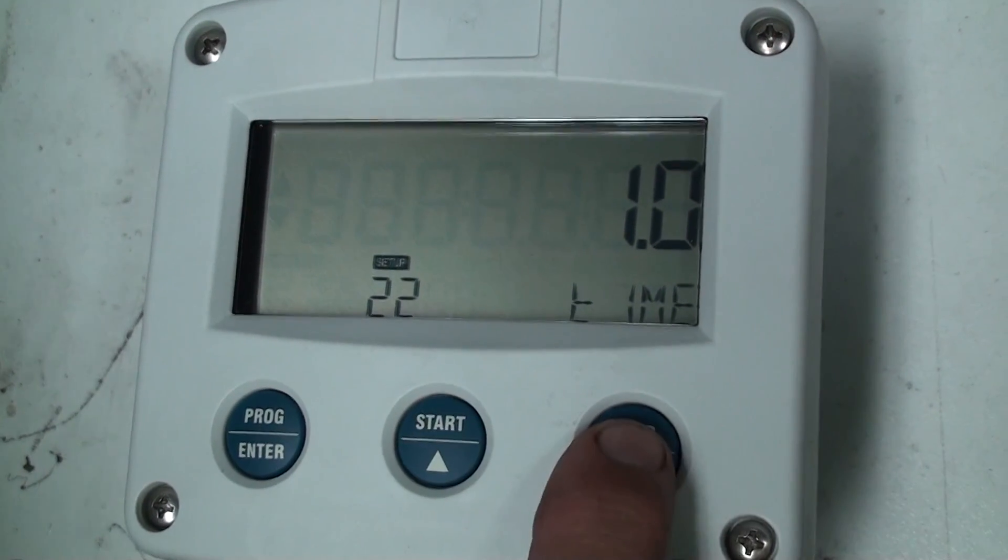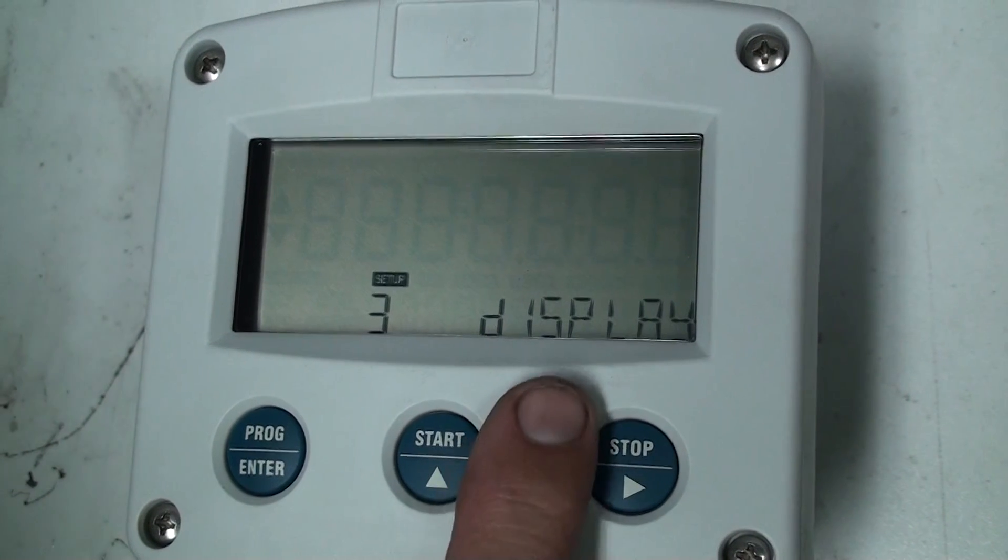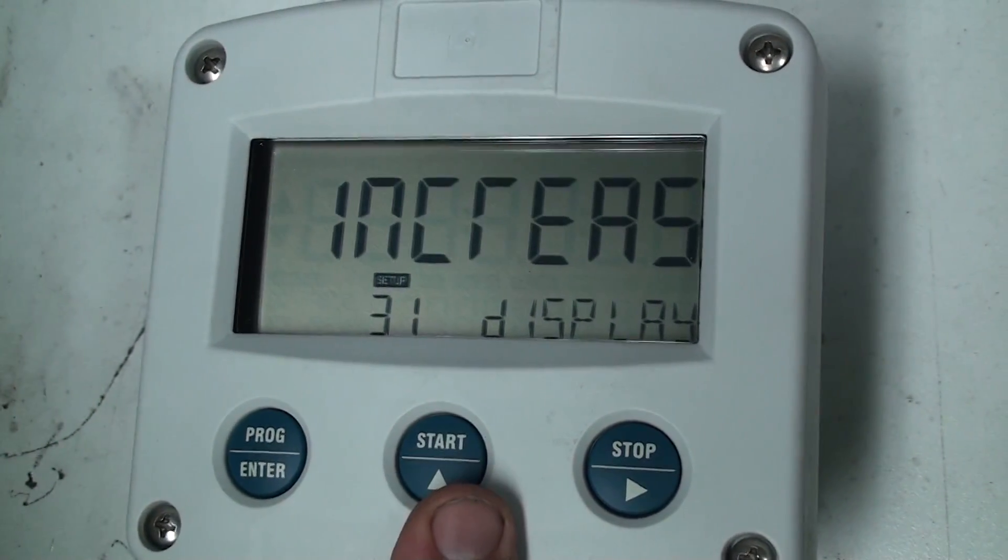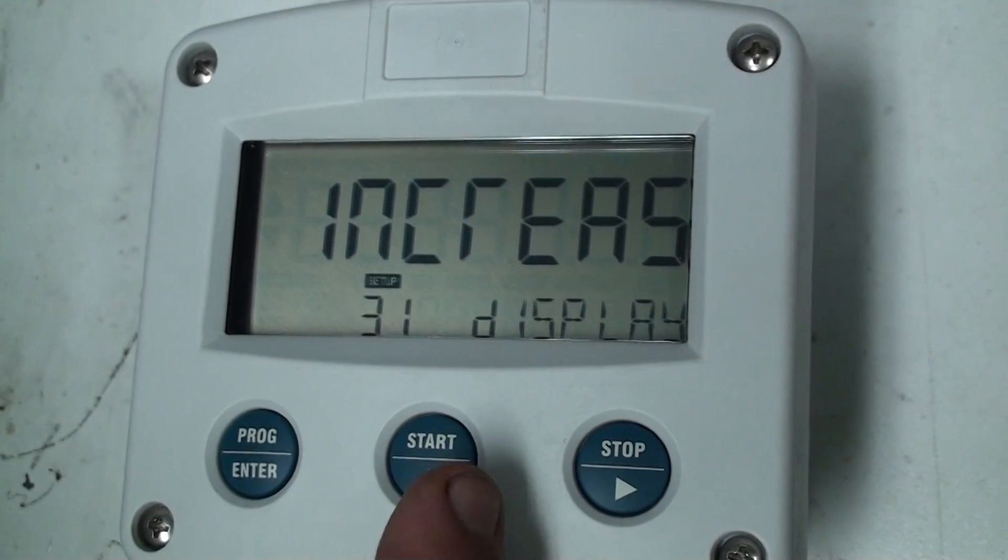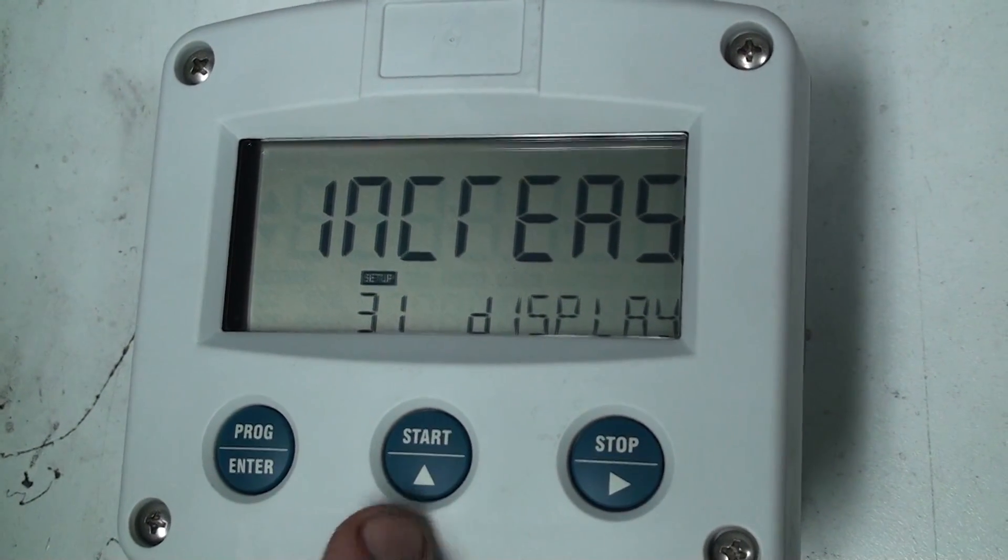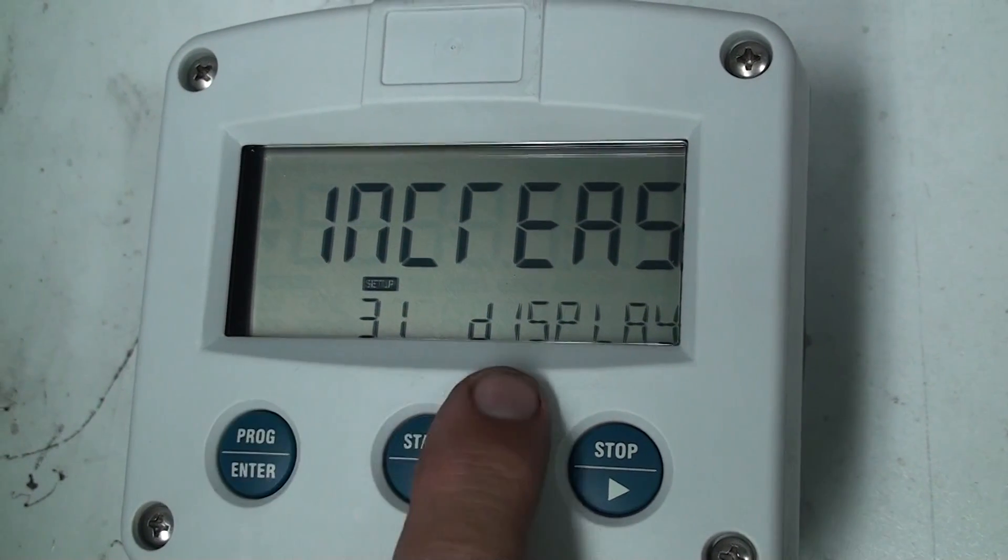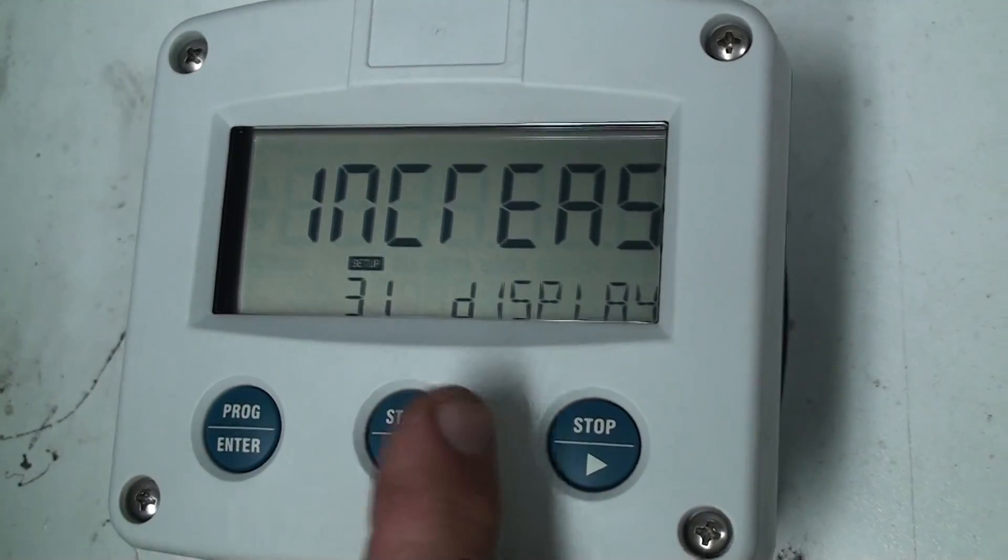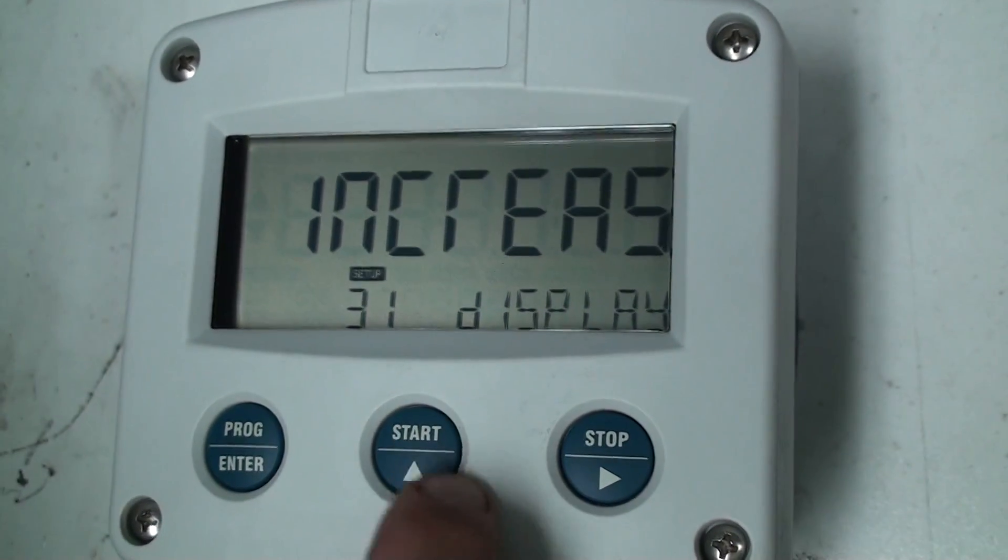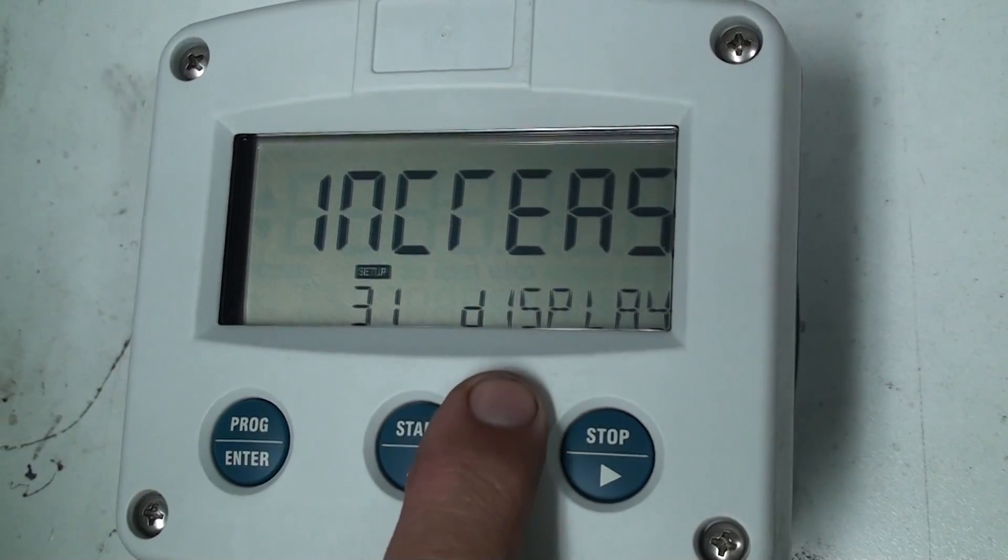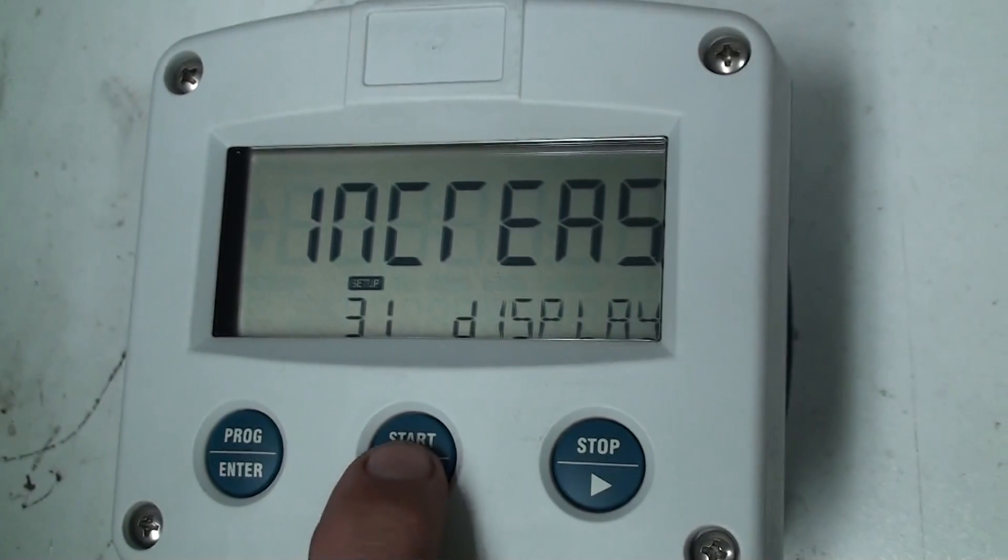We'll then go to chapter 3 and this is for your display. We scroll through 3.1 is to increase. So we're going to have the value that we're going to put in the batch to increase, so we will start from 0 and increase up. If we're batching 200 liters the display will read 0, it'll count up until it gets to 200 liters and then the controller will stop. You can have it the other way where when you press the start you can have it in decrease so that it starts off with 200 and it counts down, but we'll leave it as increase.